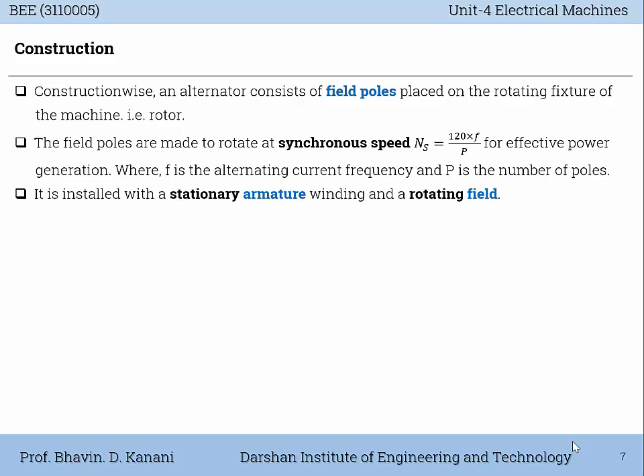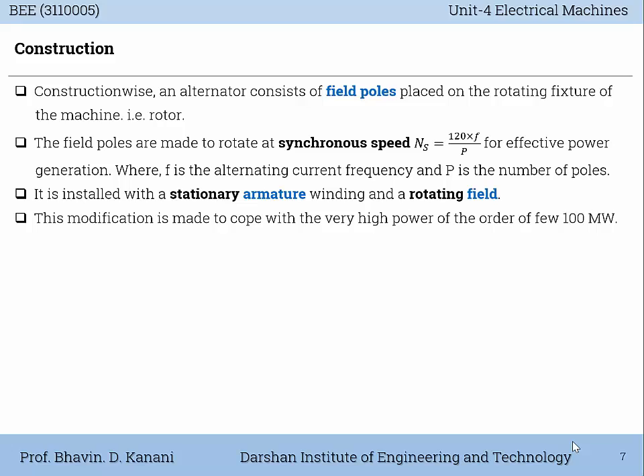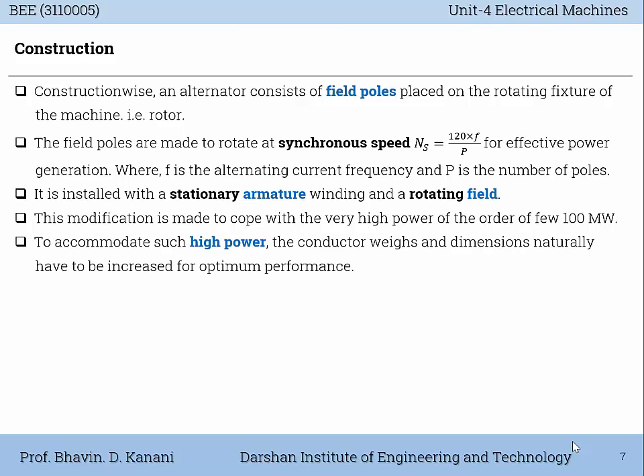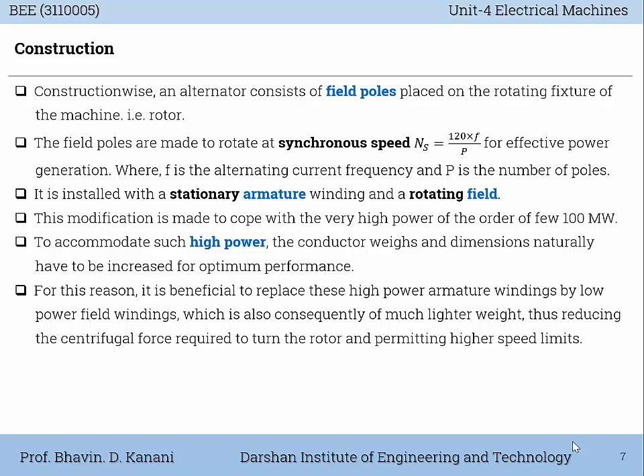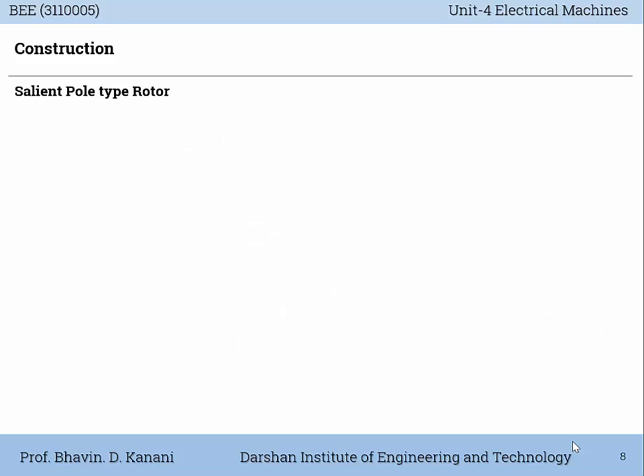It is installed with a stationary armature winding and rotating field. This modification is made to cope with the very high power of the order of a few hundred megawatts. To accommodate such high power, the conductor weights and dimensions naturally have to be increased for optimum performance. For this reason, it is beneficial to replace these high power armature windings by low power field windings, which are consequently of much lighter weight, thus reducing the centrifugal force required to turn the rotor and permitting higher speed limits.